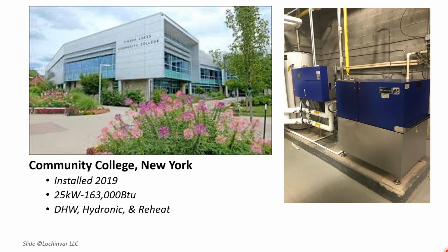Interesting fact: they use this system to fill up the hot water tanks for domestic hot water, and once that capacity is reached, they can divert the system over to their hydronic system. We installed this in the summertime, and last winter they called me with something interesting. For years they had an unresolved issue where after about 10pm when classes ended, the night setback would kick on for their main hydronic boilers, coming back on around 5am, causing a lot of condensation on interior classroom windows that was damaging the sills.